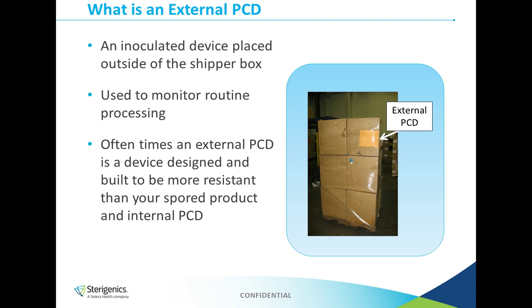And the reason that external PCD is used instead of the internal PCD is it's a lot easier to remove that external PCD from the outside of the load. Now imagine a pallet of product coming out of a chamber. It's a lot easier for the operator to walk up to that pallet and remove that external PCD than it would be to open up those shipper cases, possibly break down that pallet, and get to the product inside to pull that and have it shipped out. Not only is it not good for timing, but it's also unsafe for our employees. So a lot of times that external PCD is easier and safer.